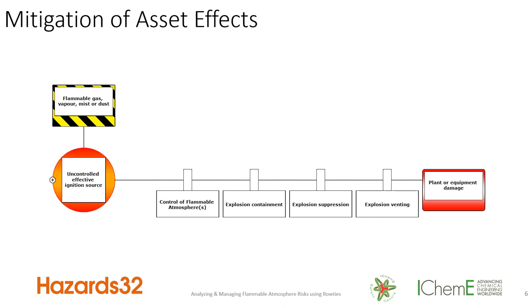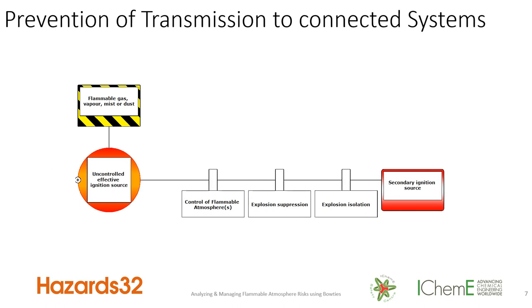Similar considerations apply for the impact on assets — plant, equipment, and structures that could be damaged — but they are generally there all of the time, so occupancy or exposure doesn't contribute to the overall risk reduction. The other measures — containment, suppression, venting, and control of atmospheres — remain relevant. And to prevent transmission to a connected system, you want to suppress the explosion or isolate it, having some means to isolate the primary and secondary locations.